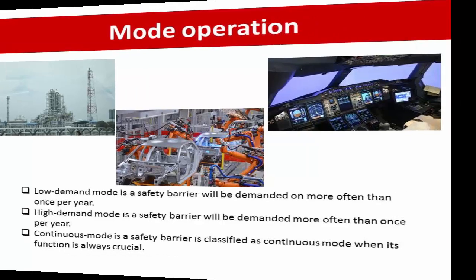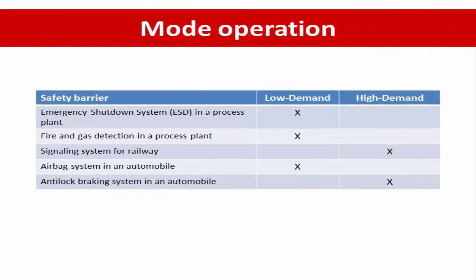This example table shows the classification of safety barriers into low demand and high demand. For example, the ESD system is classified as low demand. Fire and gas detection in a process plant is classified as low demand. Signaling systems for railways are classified as high demand. The airbag system in a car is classified as low demand, and the anti-lock braking system in an automobile is considered high demand.